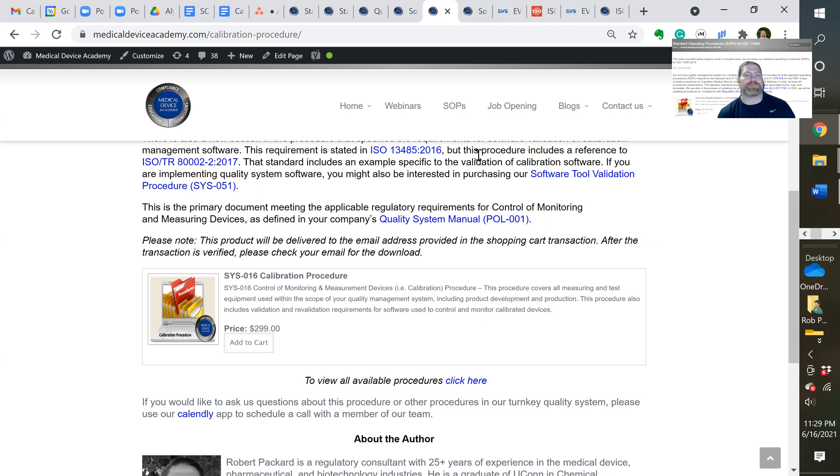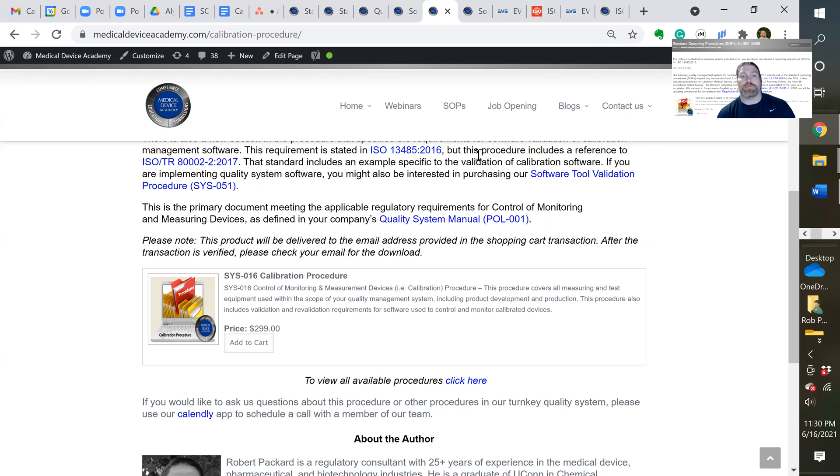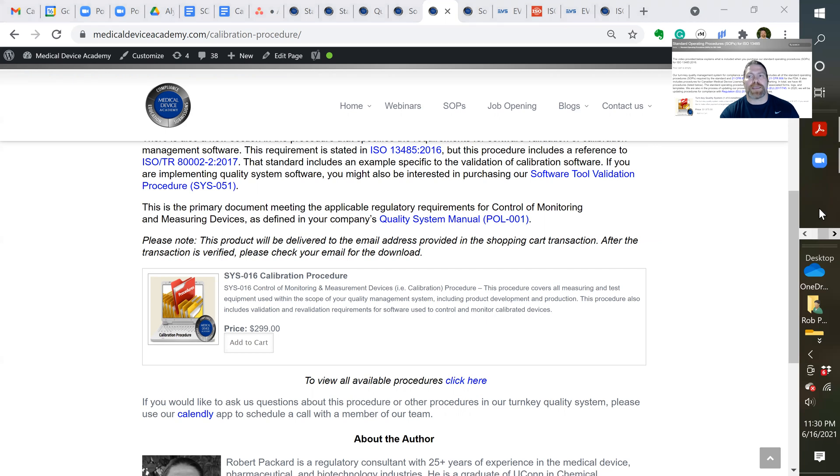Well, what about Europe? Everybody's asking me, oh, we just, on May 26, we had the MDR take effect in Europe. Is your procedure been updated for that? Well, no, there was no update required, because there isn't a specific requirement in the MDR for Europe for a calibration procedure.